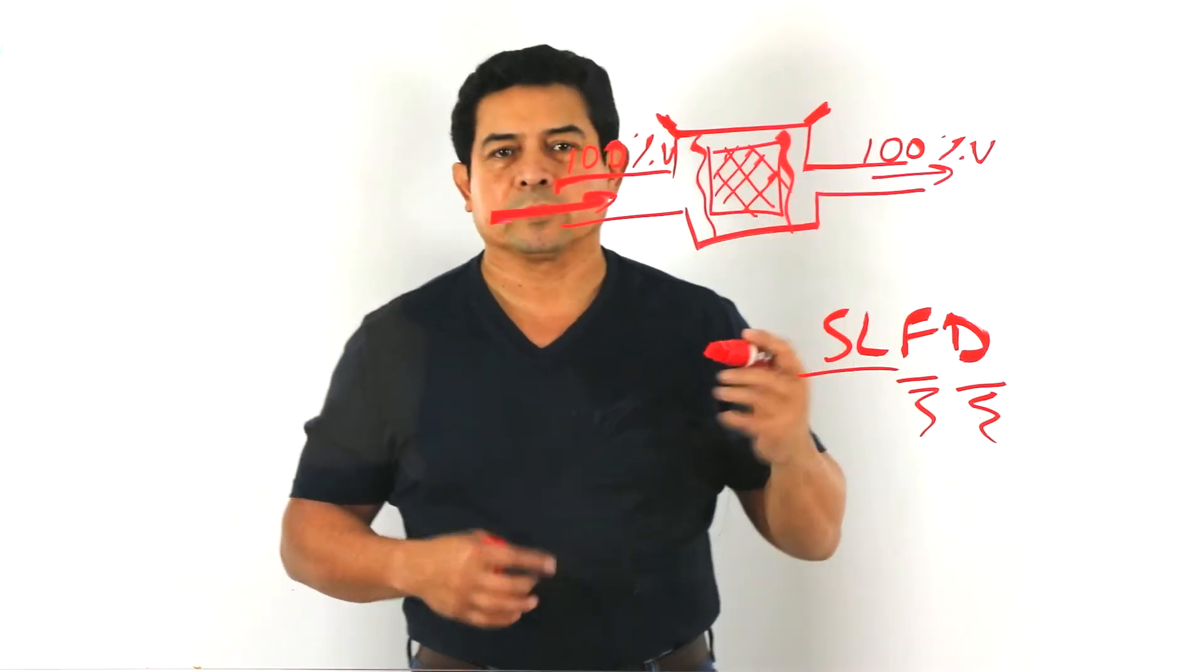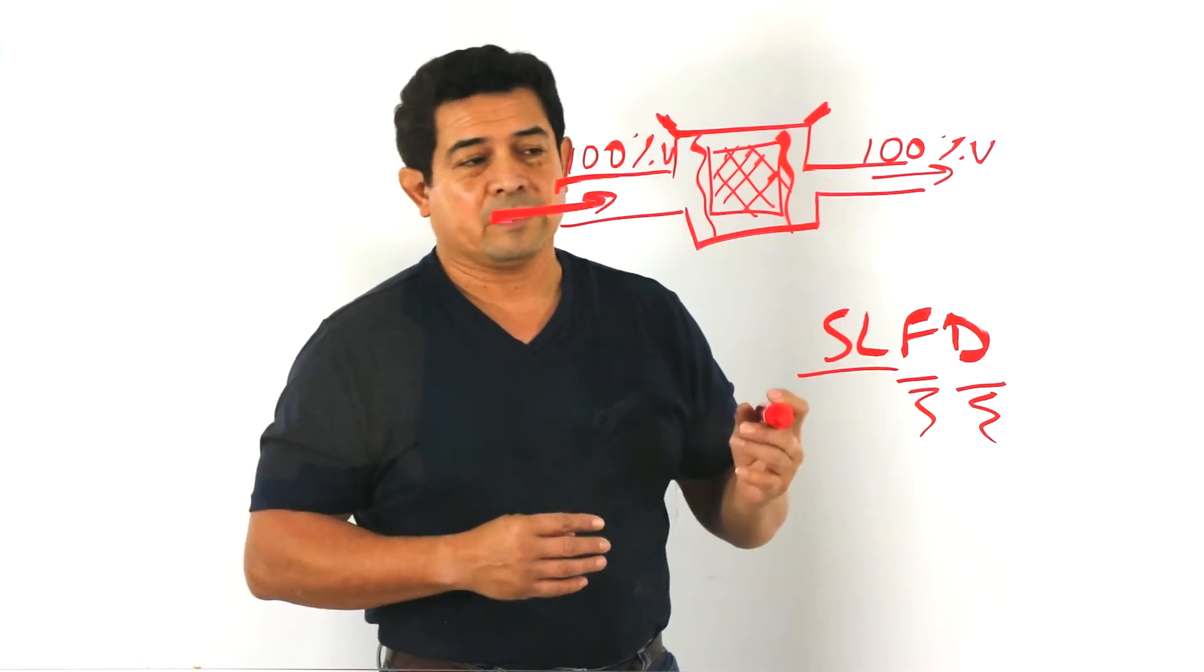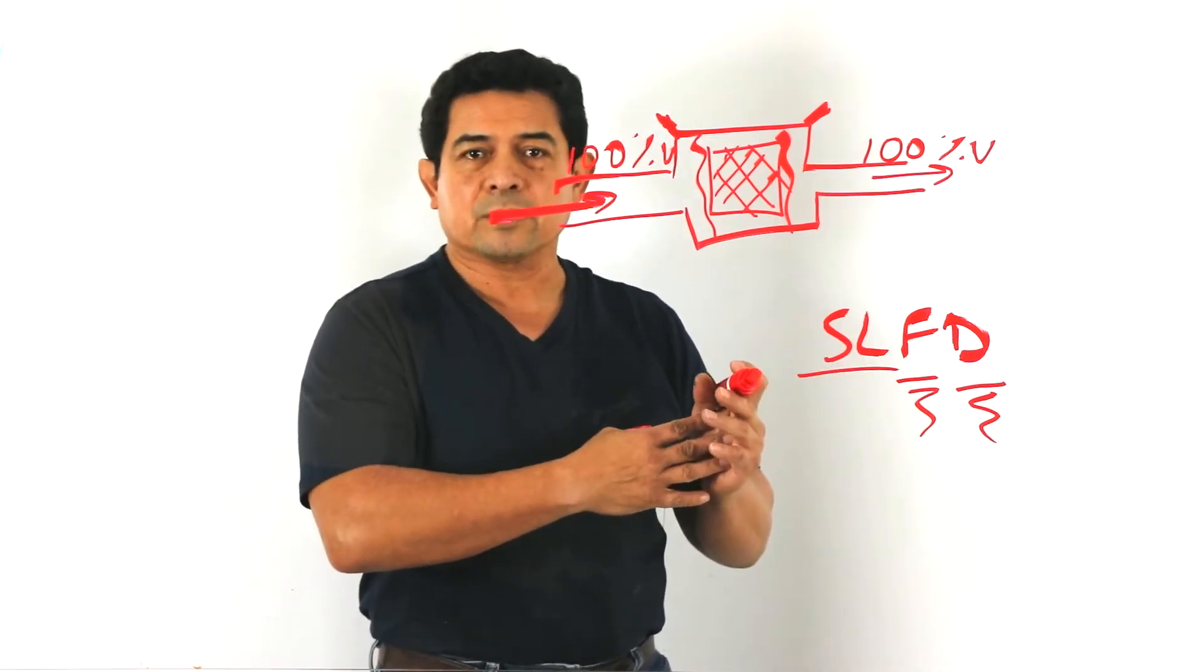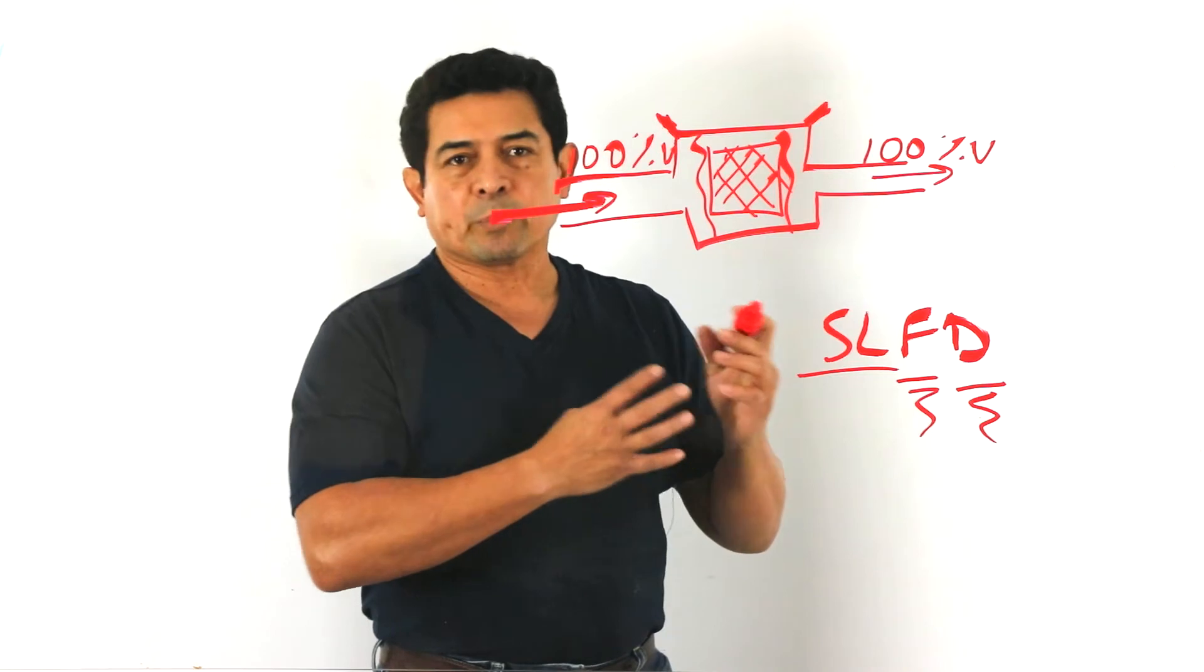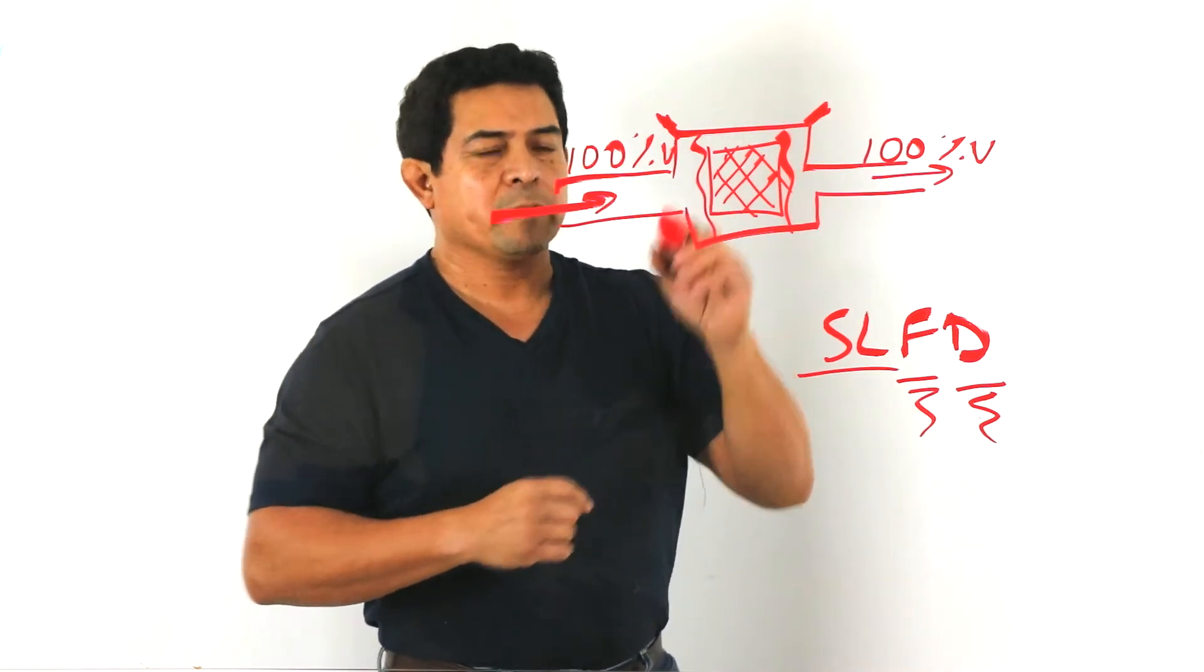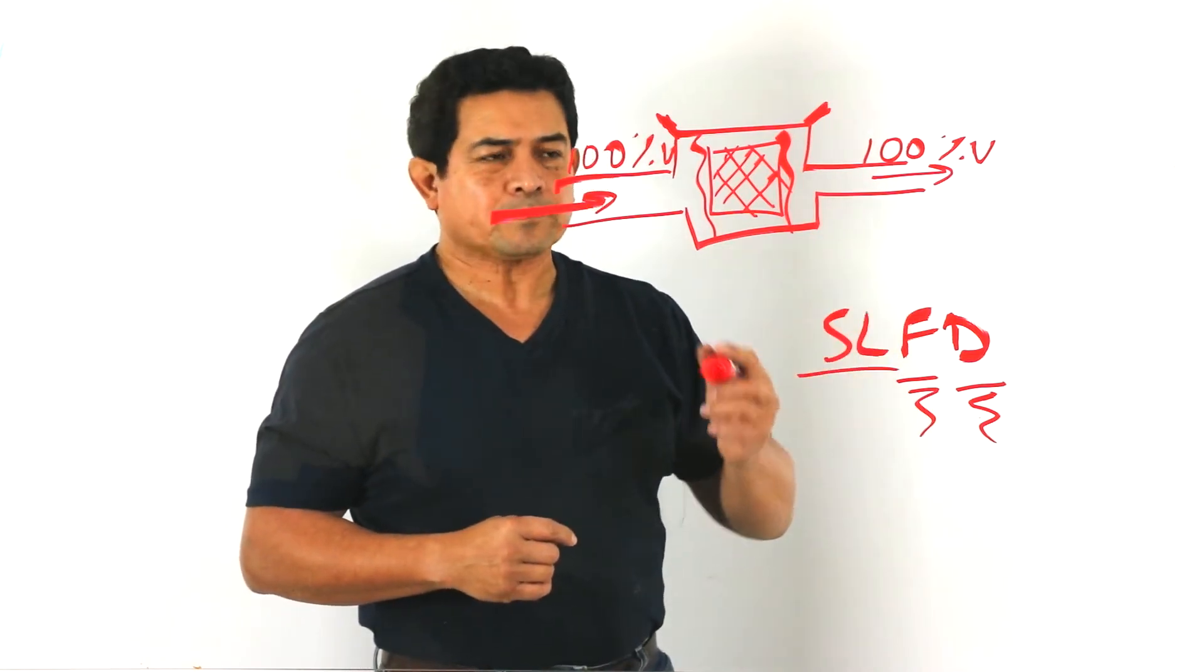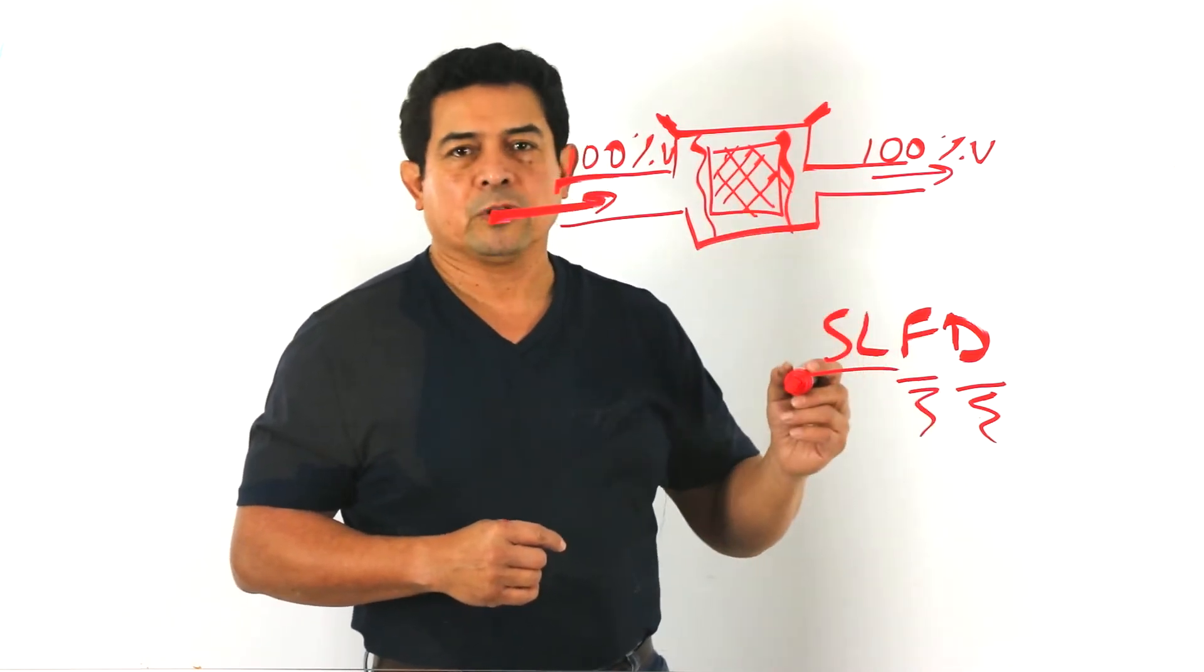Here we're going to filter, we're going to trap all the trash that's in the system. Because like it or not, we get stuff in the system when we install it, when we do the installation or when we replace a part. So we want to make sure they don't get to the compressor or the metering device. That's why we need to filter what's in there.